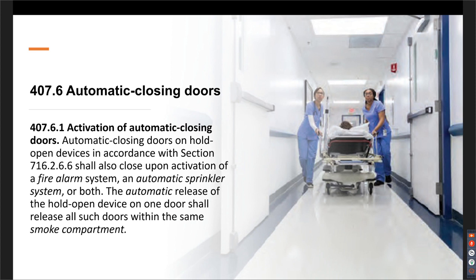So for those auto-closing doors that are on hold-open devices, they have to close upon activation of the fire alarm, sprinkler, or both. That's not a pick one. You got it. It's tied to the fire alarm. They're tied to the sprinkler.